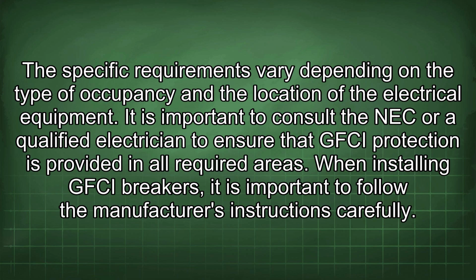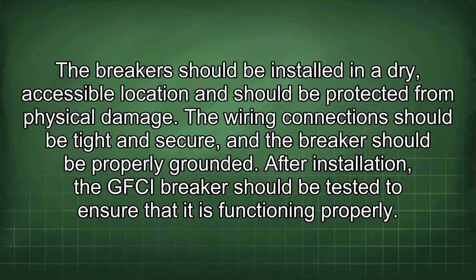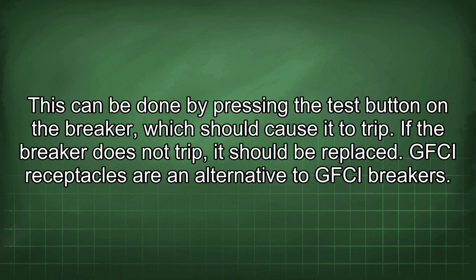When installing GFCI breakers, it is important to follow the manufacturer's instructions carefully. The breaker should be installed in a dry, accessible location and should be protected from physical damage. The wiring connection should be tight and secure, and the breaker should be properly grounded. After installation, the GFCI breaker should be tested to ensure that it is functioning properly. This can be done by pressing the test button on the breaker, which should cause it to trip. If the breaker does not trip, it should be replaced.